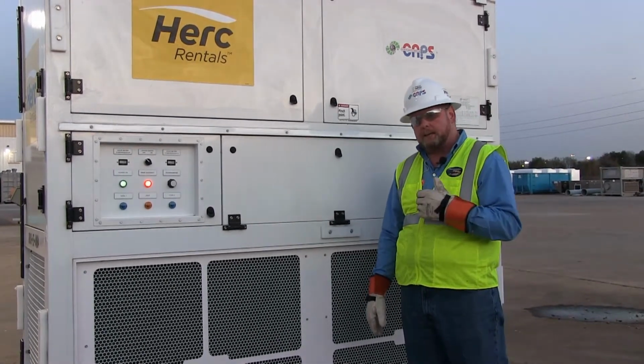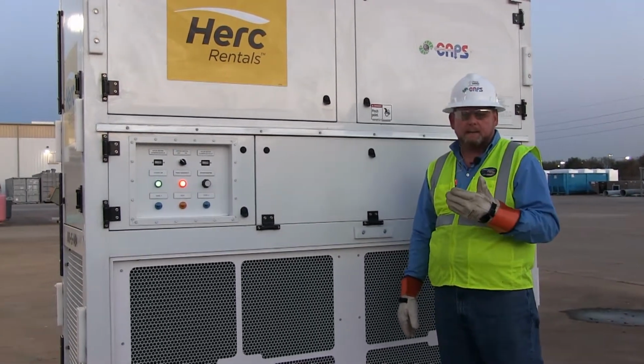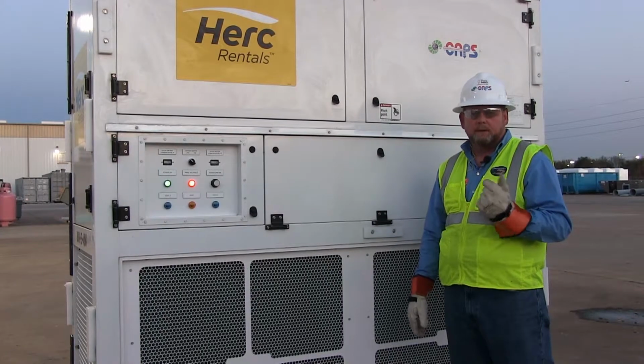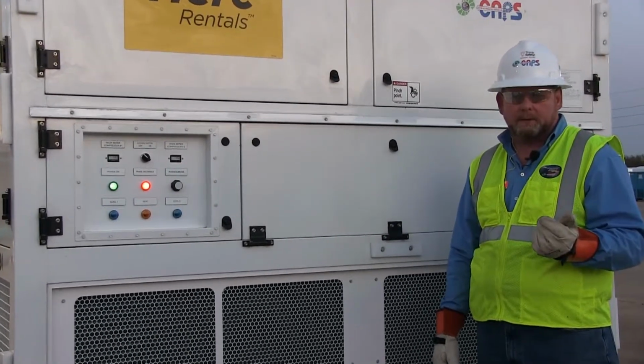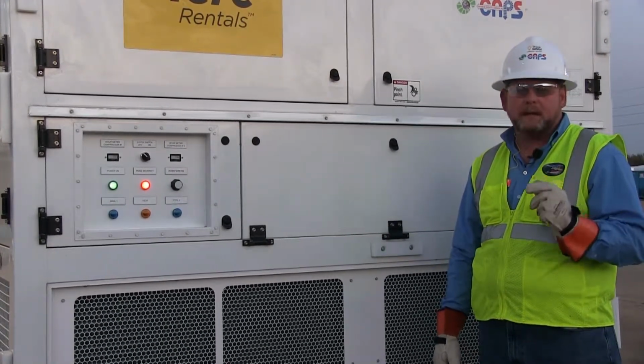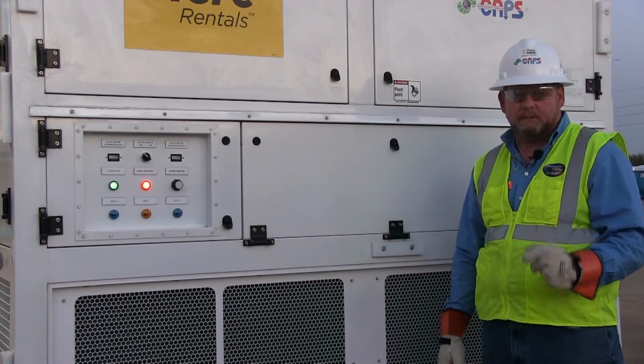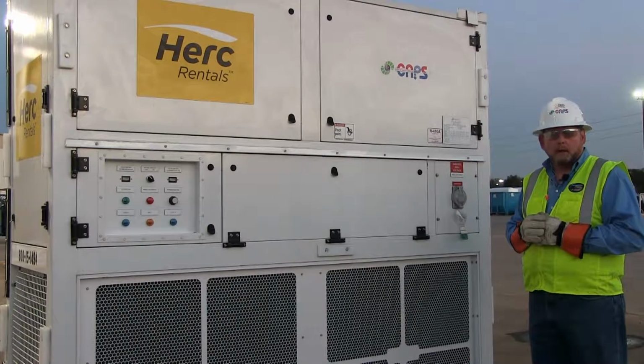Now we're going to disconnect the circuit breaker and lock out and tag out our main power source so that we can change the cam lock connections. Please note that you do not change the cam locks while they're energized. Okay, we reversed two of the incoming leads.